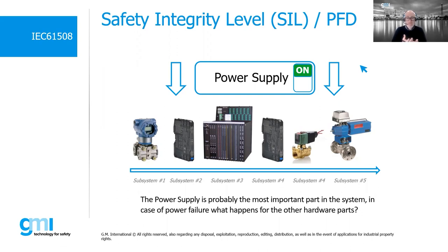This helps us to have a safety loop and, with the correct redundancy, a loop with high availability to the process. The slide shows our safety loop made up of all its elements, correctly sized and SIL certified, to get the most out of the functional safety of our system.